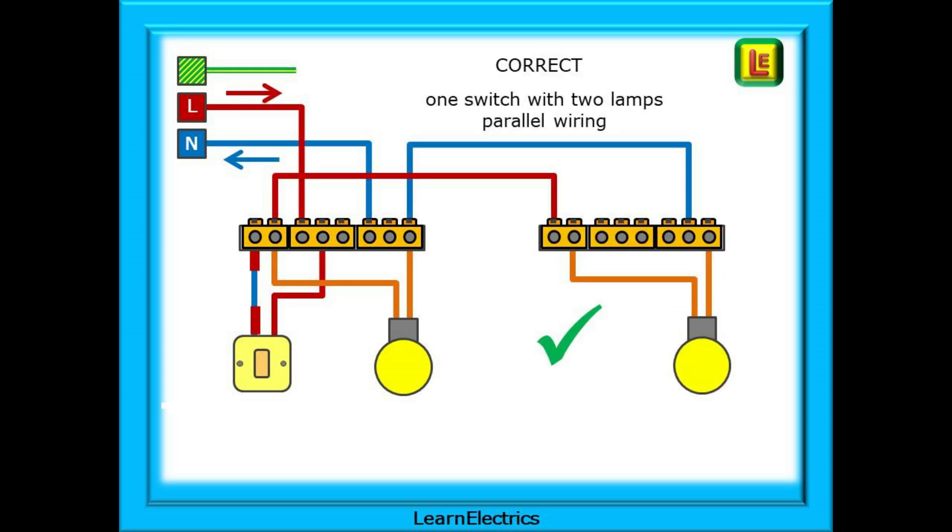Now we can add a second lamp in parallel with the first. When lamp one comes on, so does lamp two. This has been achieved by connecting together the switch blocks in the two ceiling roses, and then connecting together the neutral blocks in each ceiling rose. Attach your second lamp between them, and all is good.